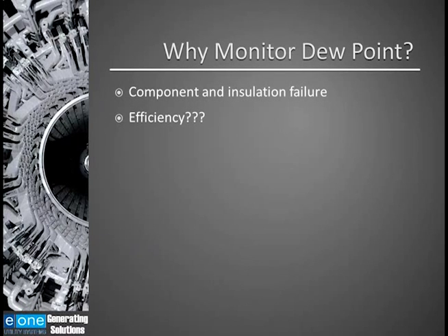What is a good dew point? Zero is usually the alarm point that most OEMs recommend. So you want the dew point to be lower than 0. Hydrogen from bottles or bulk systems is usually very dry. However, it is possible to get a bottle of wet hydrogen. It's rare, but it can happen. Hydrogen produced by hydrogen generators is always dry. So where does the moisture come from? In most cases, the seal oil or the cooling water, or if your generator stator is cooled with water, it could come from the stator cooling water.